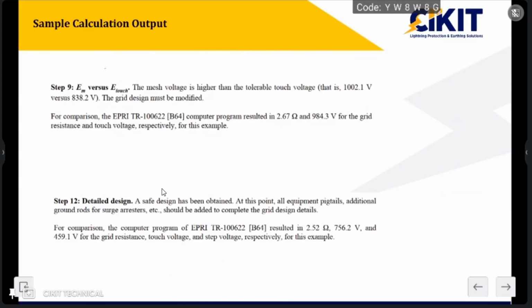So here we have shown the sample calculation from the standard. In the initial stage they have taken a square configuration of the earth grid, without earth electrodes, and they found that the values of step and touch voltages are not within the limit. The mesh voltage calculated is higher than the tolerable limit: 1002 is the mesh voltage and 838 is the tolerable value. Since the mesh voltage is higher than the tolerable limit, the design is not safe. So we are making a modification.